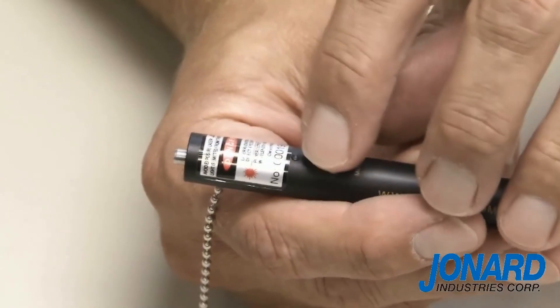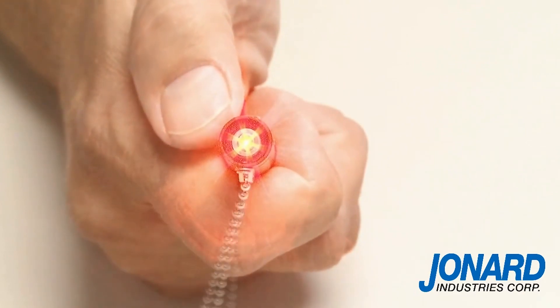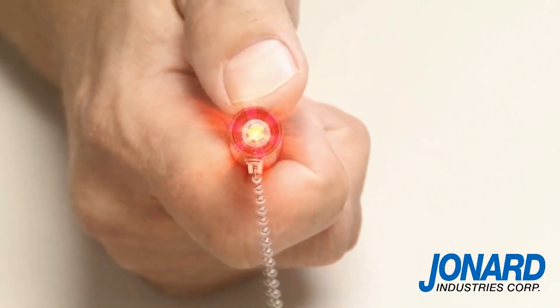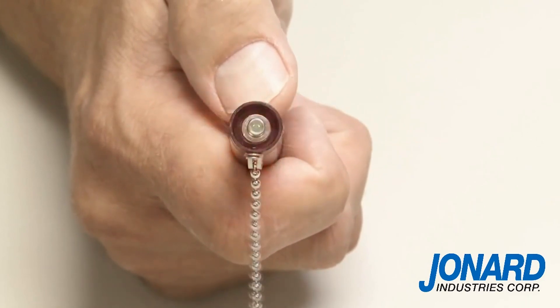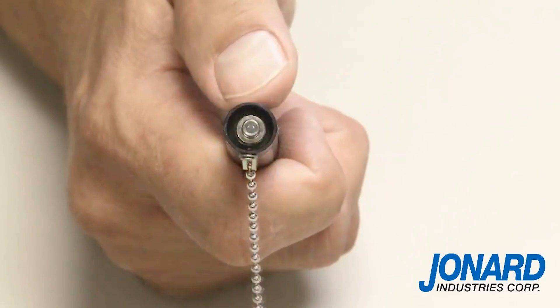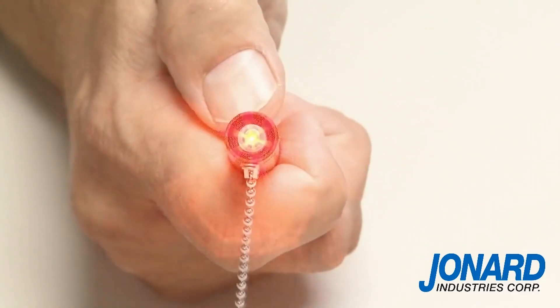Press the mode switch to activate the laser. A continuous red beam will emanate from the VFL25 at the 2.5 millimeter universal connector. Press the mode switch again and the red beam will pulse at 6 to 9 hertz frequency. Press it again and the beam will pulse at a slower 1 to 2 hertz frequency. Press the mode switch a fourth time and the laser will shut off.